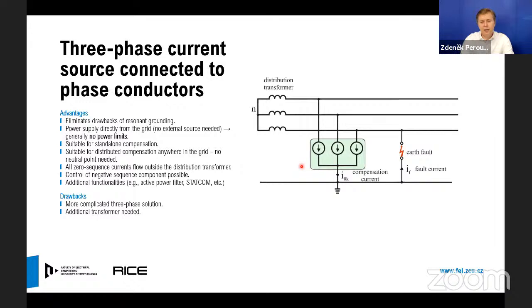This device is suitable for distributed compensation, which means that it can be installed anywhere in the grid. We do not need a neutral point for the installation of this device. All zero sequence currents flow outside the distribution transformer, and we can control positive, negative, as well as zero sequence component. And we can offer in this configuration additional functionalities such as active power filtering, STATCOM functionality, and many other features. The penalty for this configuration is higher cost, and we need an additional transformer to be able to connect this device into the grid.